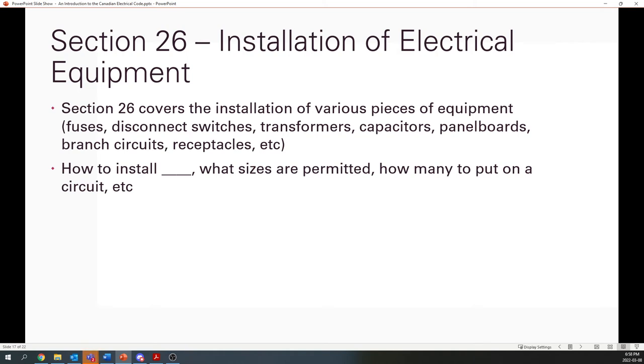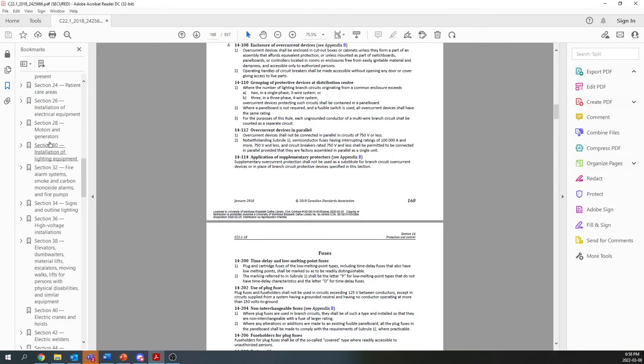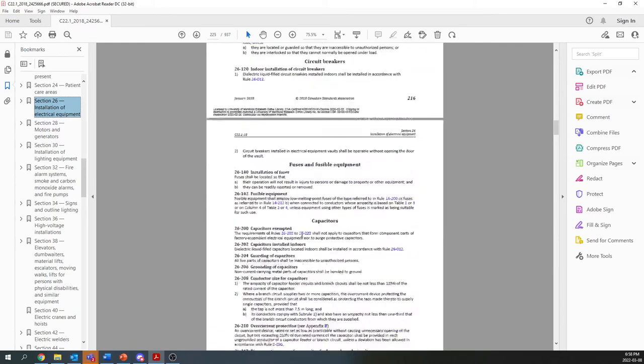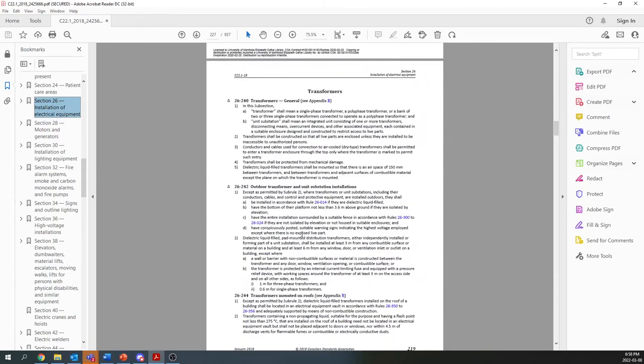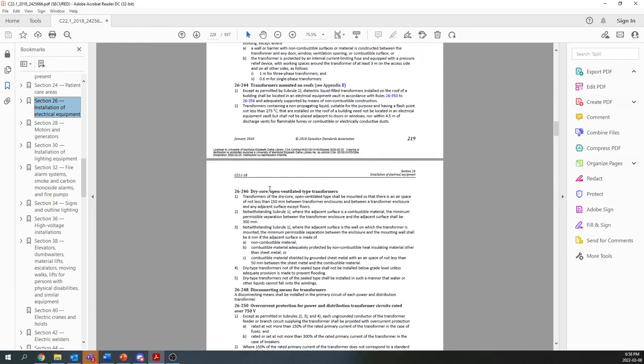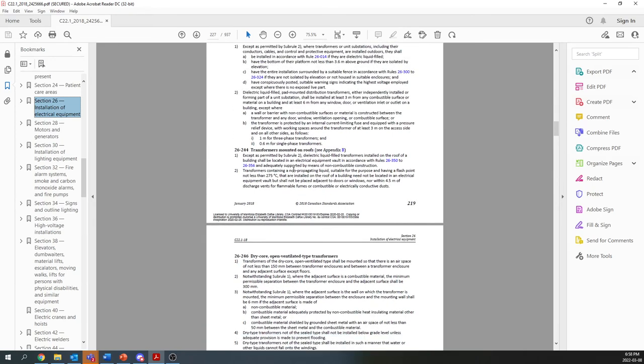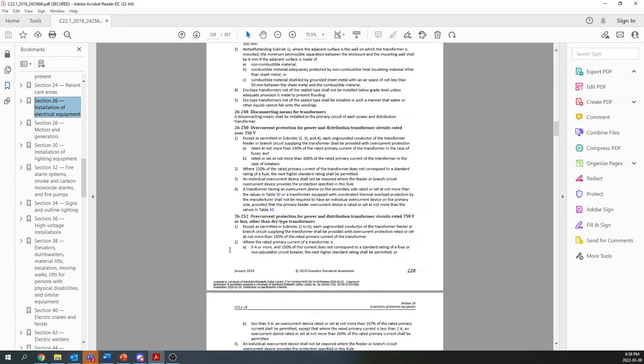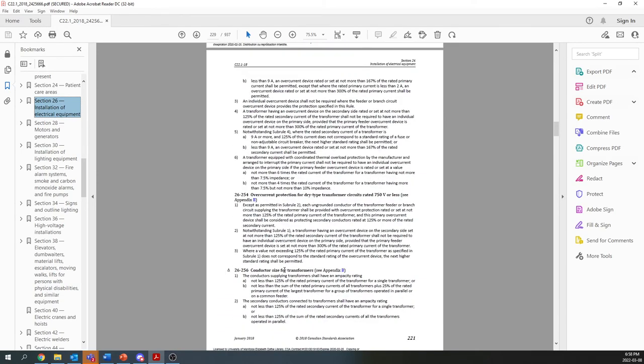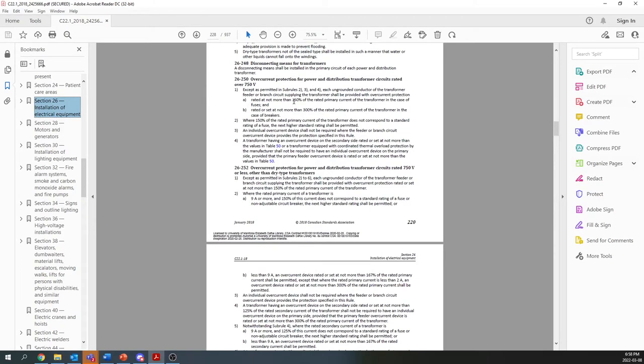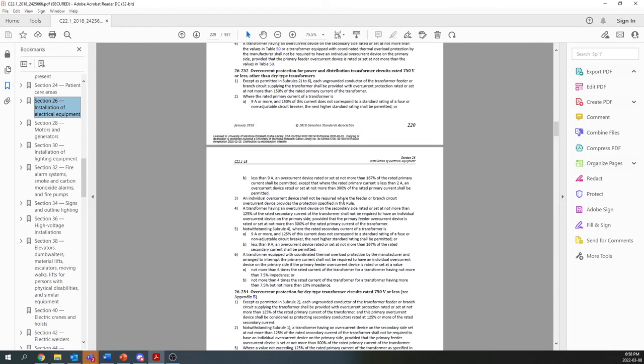So now, this being said, section 26 also covers a lot of rules for the rating of overcurrent devices, for example, transformers. There's a lot of rules in section 26 on transformers. So, for example, take a look at this here. Transformers. These are all different types of transformers, different installation types of transformers, and 26-250, 26-252, 254, 256 are kind of the main ones that set the overcurrent protection that you need to look at if you are designing a system with transformers.